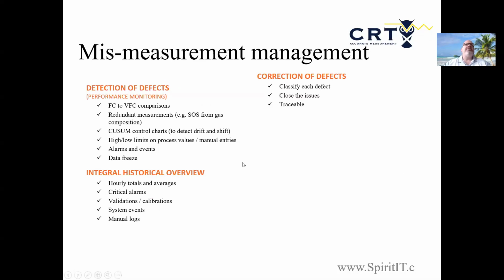I spoke briefly about mismeasurement management, but it's a way for a flow computer and a virtual flow computer to do comparisons, to have redundant measurement, to have high and low limits on process values, to bring back your alarms and events and store them along with other information. Remember, a flow computer has a finite amount of data storage inside of it. If I'm able to bring that into a mismeasurement management system, then that information goes from being stored locally for 30 days or 6 months, depending on storage space in the flow computer, to now being stored for decades, or whatever your data retention policy is within your company.